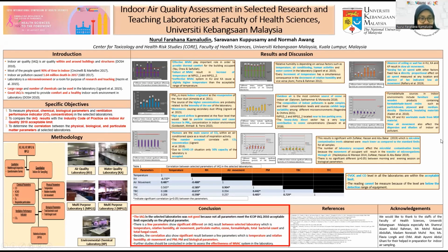And to conclude, the IAQ in the selected laboratories was not good because not all parameters meet the ICOP-IAQ 2010 acceptable limit, especially on the physical parameters. Further studies should be conducted to assess the effectiveness of the MVAC system in the laboratory.